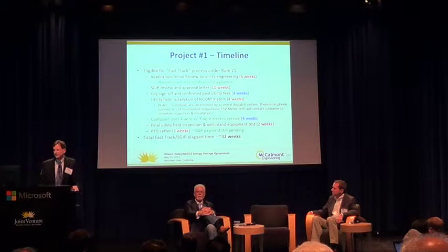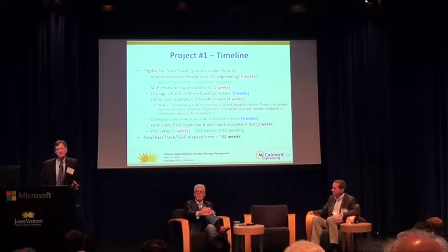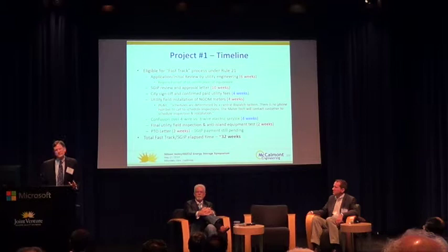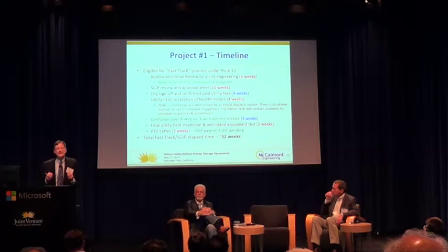But one of the challenges with these systems is all of them are quite young in the market, and so UL listing and UL certification is something that's still getting figured out. Batteries now fall under UL 1973, which is a fairly recent standard. Solar inverters fall under UL 1741 for non-exported power, which is a standard that's been around for a while, but the integration of those two standards really hasn't been well addressed yet. And UL is working on a combined standard for energy storage. I imagine it'll be several years before that becomes available.